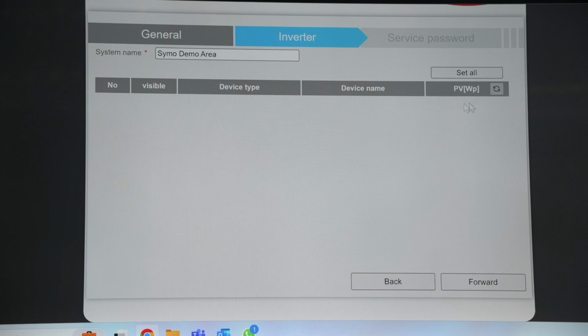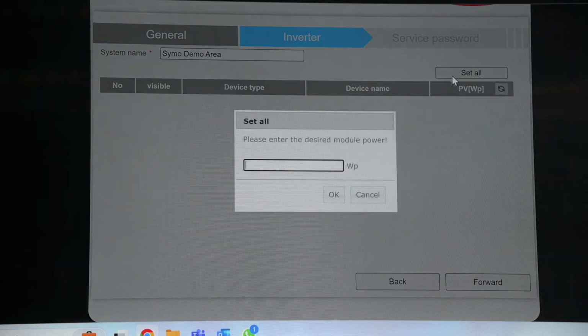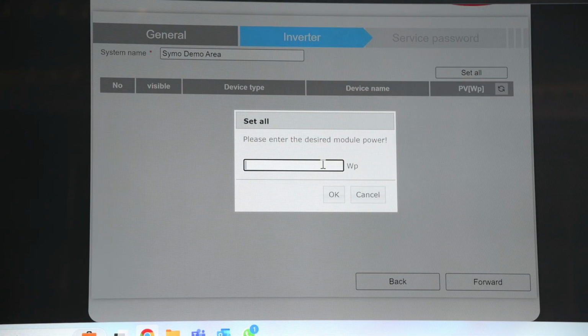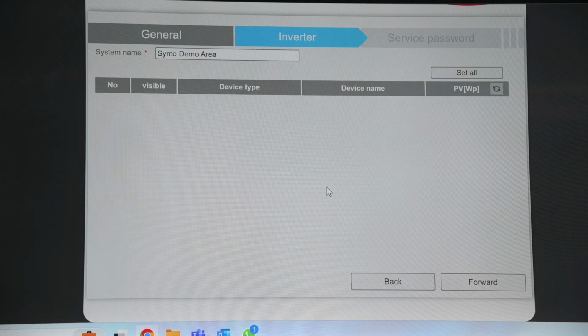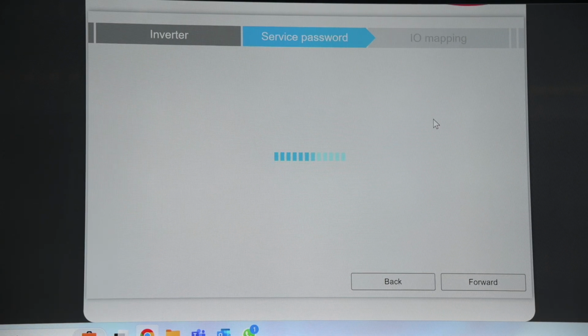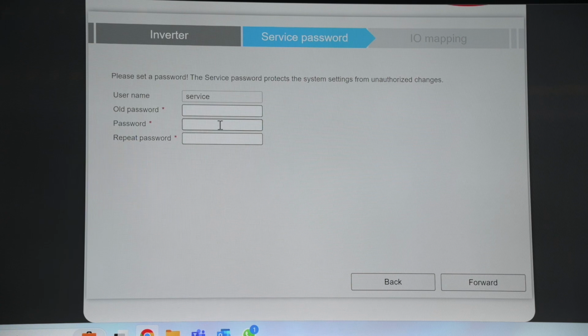Lastly, what we need to add is our PV watt peak. So this is the kilowatt peak on the DC side that has been connected to the inverter itself. If, for example, we're doing an installation where we're using an Eco 27 and we've oversized it to 28 kilowatts, we can set all Eco 27s to be oversized to 28 kilowatts, so you don't have to go individually and separately input that data. So once we have set that data, forward. Now this is where you would set your service password for the unit.